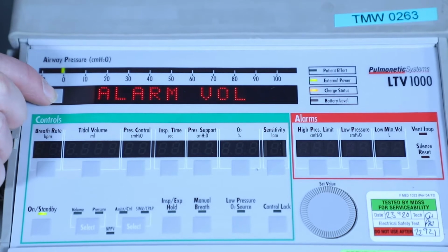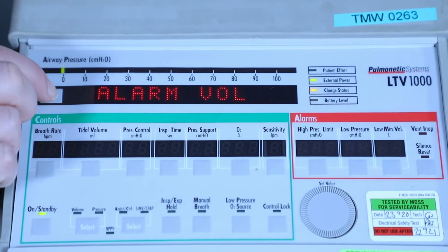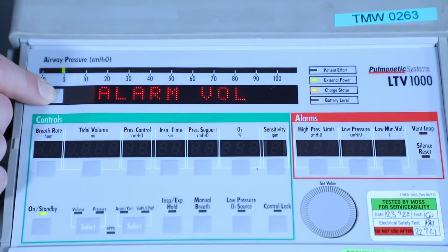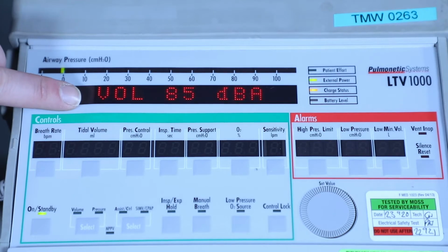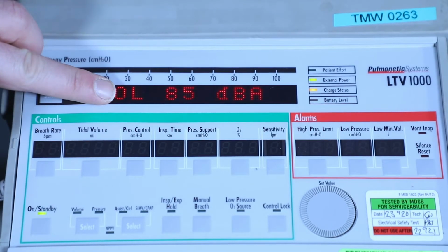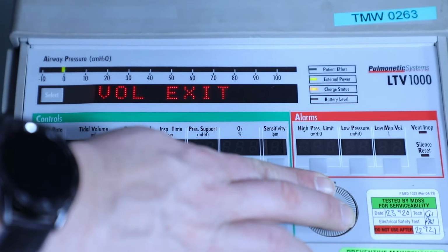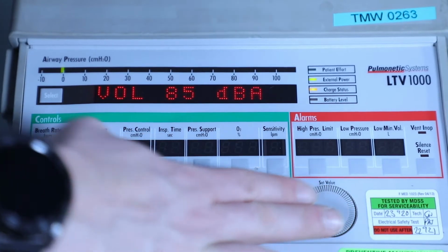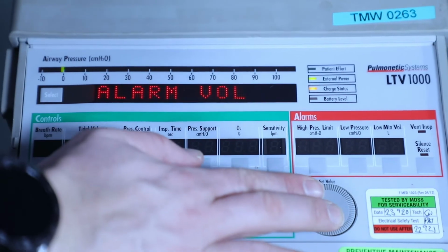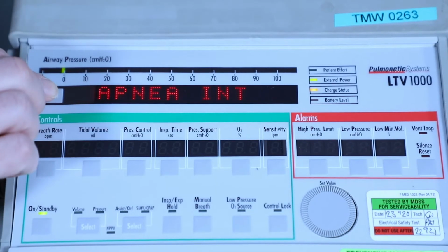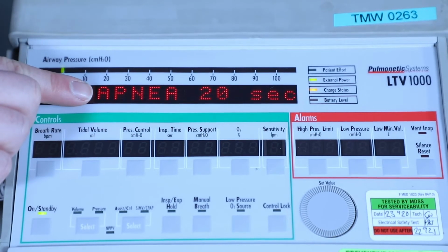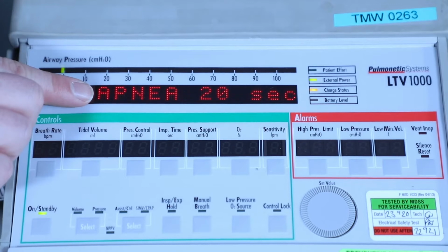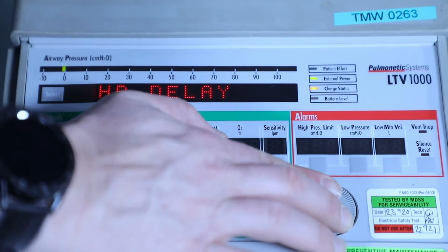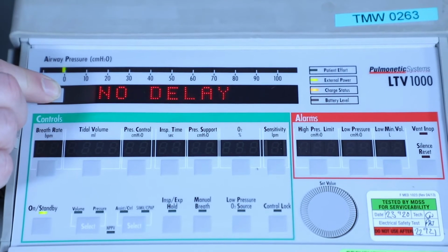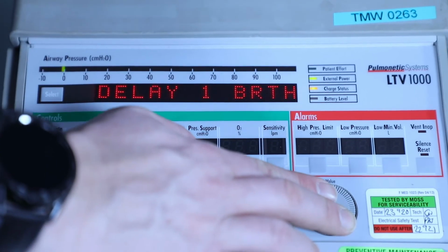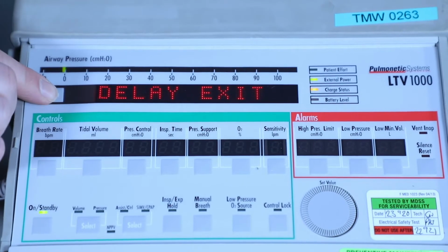Press the select, and we're going to scroll through each of these menus to ensure that the correct parameters are displayed. The volume ranges between 65 and 85 decibels. We keep it at 85 decibels. Press the select, and on to the next menu. Current apnea settings should be 20 seconds. The device has a range between 10 and 60 seconds. High pressure delay can be set to no delay, 1 breath or 2 breaths. We currently set to no delay.